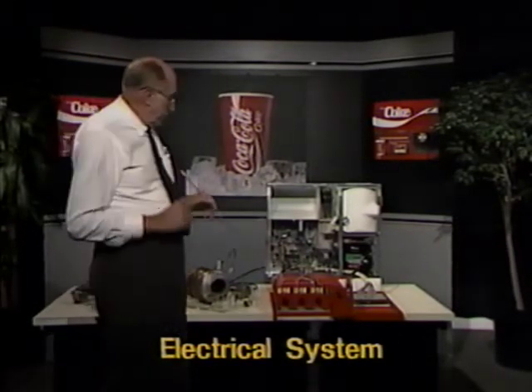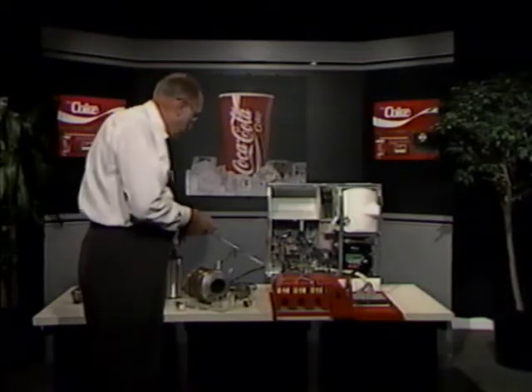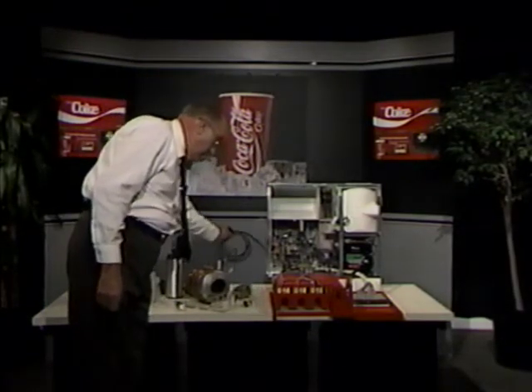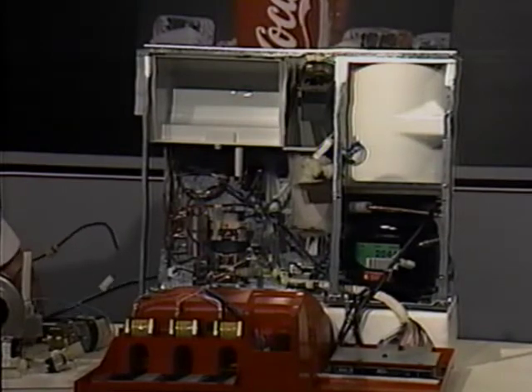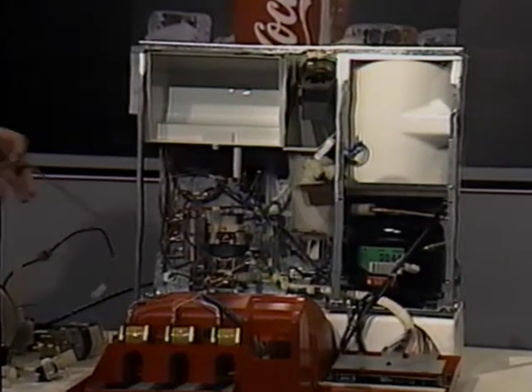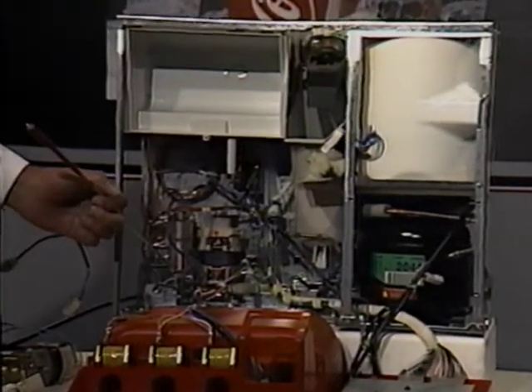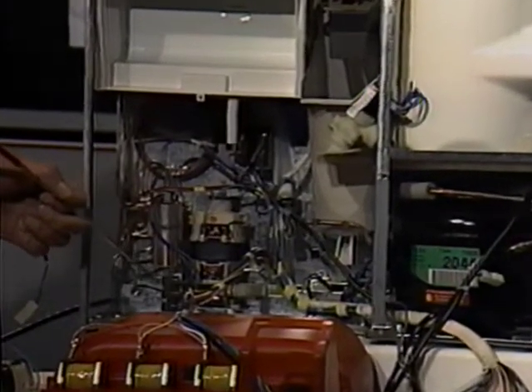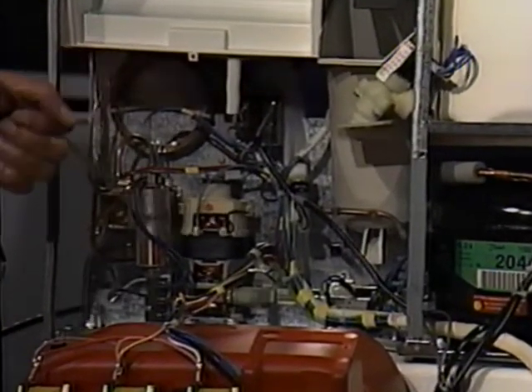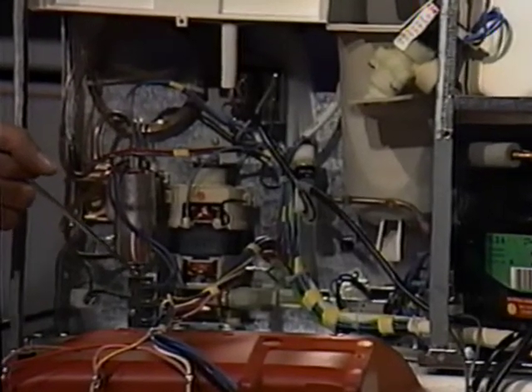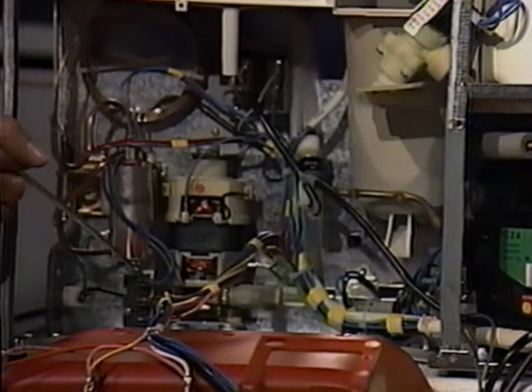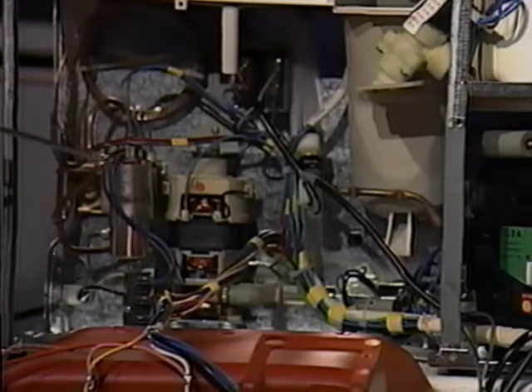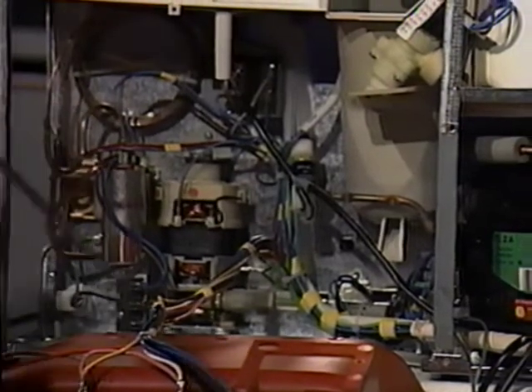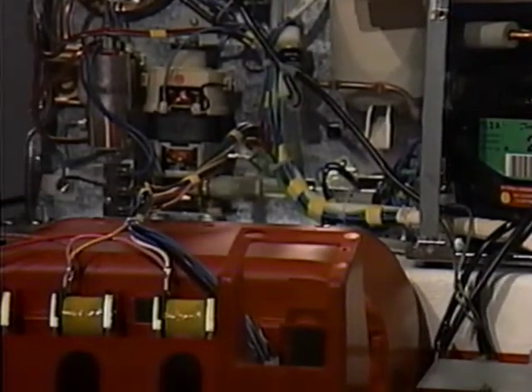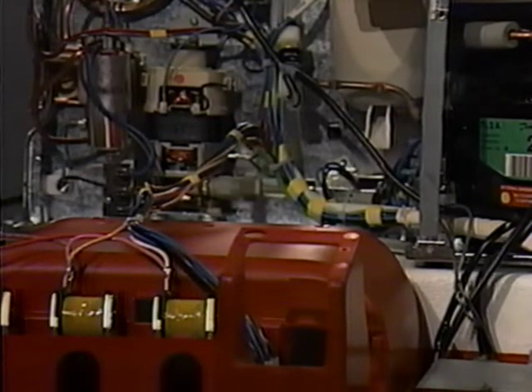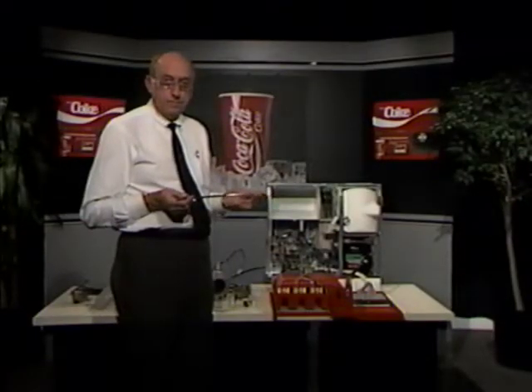Power is supplied to the dispenser through the line cord coming into the back of the dispenser. It comes in and is connected to an inlet filter which prevents electrical interference from going back into the power line. From there, the power line is fed into the main switch on the dispenser. That's a two-pole switch which cuts both sides of the line.